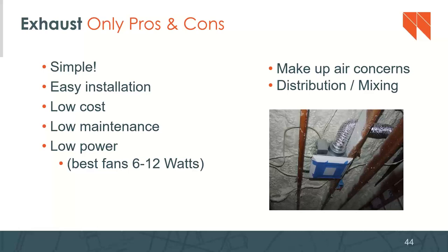Another con of exhaust only is the distribution and mixing of that fresh air. So you're sucking on the home, pulling that air out, and that fresh outside air is going to come through that path of least resistance. Is it necessarily going to make it to the people who need the fresh air, i.e. the humans living in there? It's anybody's guess. It's not an intentional system in terms of distributing this fresh air to where it needs to go. The building doesn't need fresh air. The occupants need this fresh air, this ventilation.